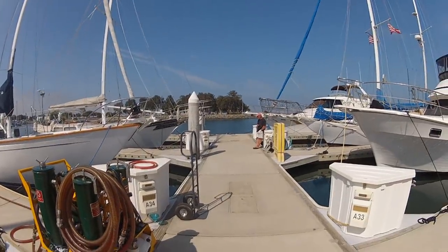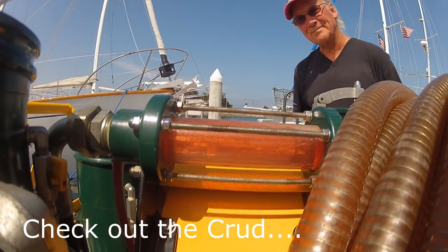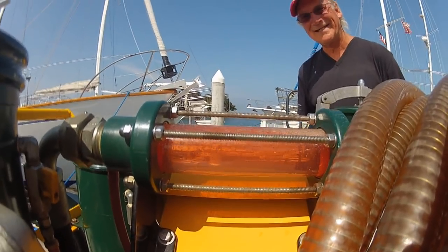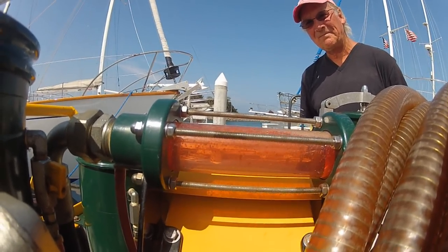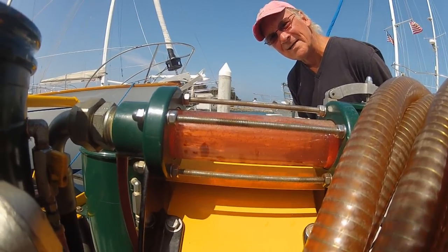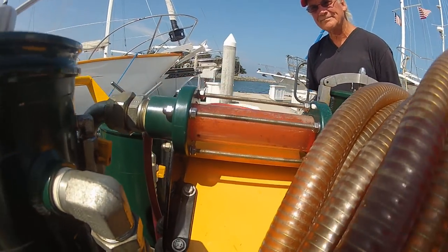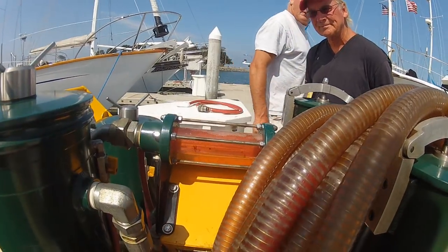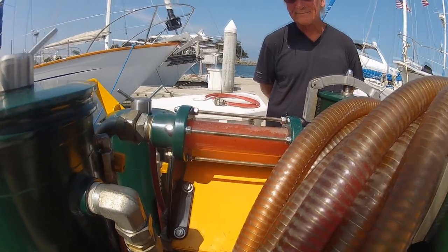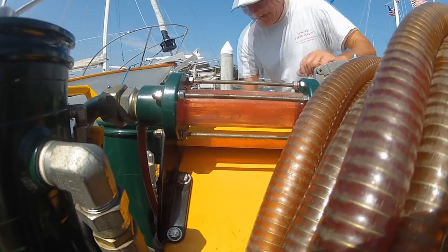There's Tony the local expert. You can see junk going through the filter - the glass tube. It must have been in his hose. He took that hose and ran it back and forth a few times. Look at it - there's a lot of material, aluminum chips going by. Oh yeah, nice and shiny.